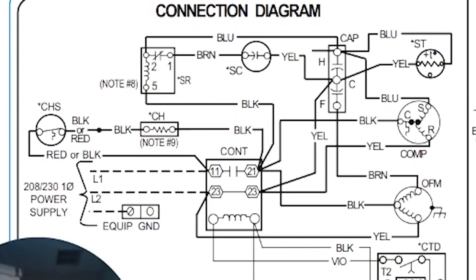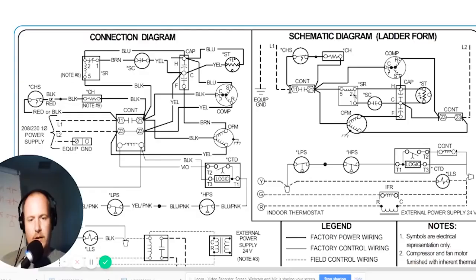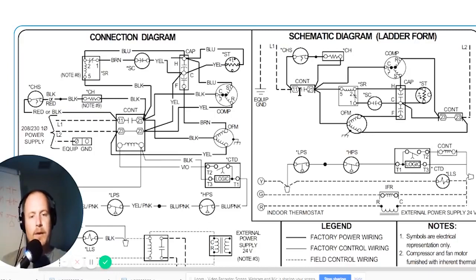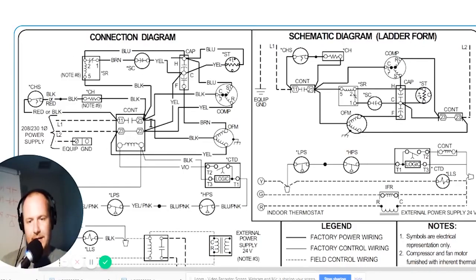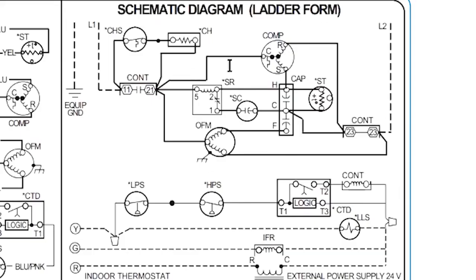We only show the contacts up on the high voltage side, separate from the contactor coil, because this is a ladder schematic style diagram. Over on the connection diagram on the left, the contactor has everything all together — the coil, the bar across it (this is a single-pole contactor), and the contacts. The contacts are numbered, so you can reference connection point 11 on the contactor whether looking at the schematic or the connection diagram — they're the same thing.